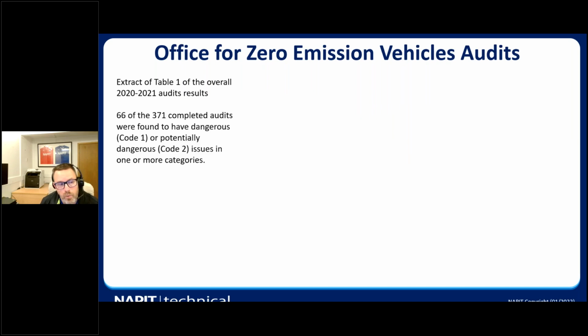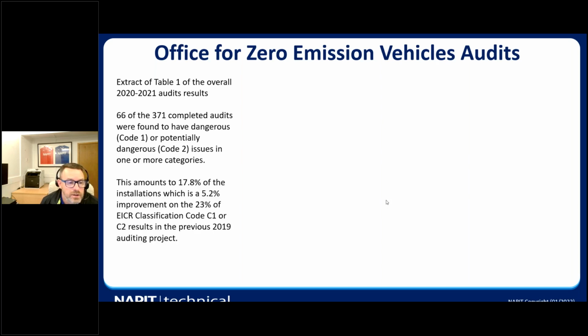An extract of Table 1 for the overall 2021 audit results. And 66 of the 371 completed audits were found to have dangerous C1 or potentially dangerous C2 issues in one or more categories. And as I said, the auditors used the EICR reference method codings, which because of new installations would be non-compliant with BS 7671. And this amounted to 17.8% of the installations, which is a 5.2 improvement on the 23% EICR classification codes, C1s and C2s, from the 2019 audit. So there has been an improvement.